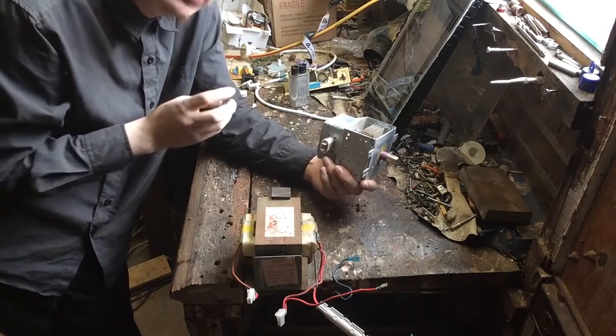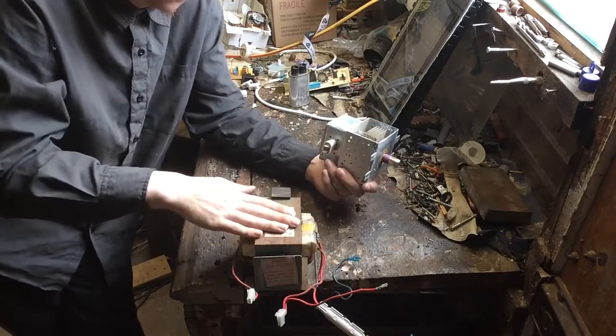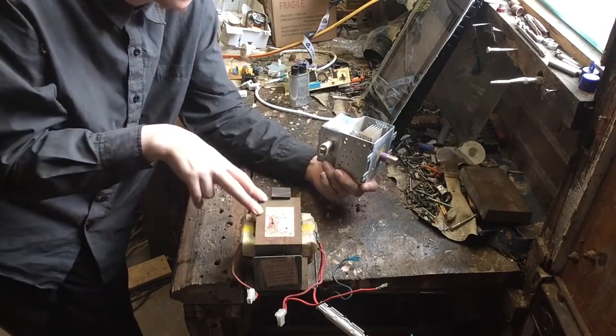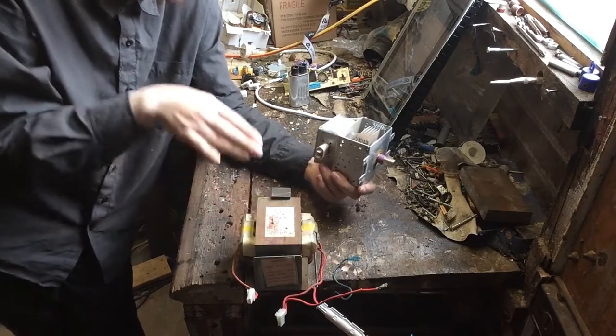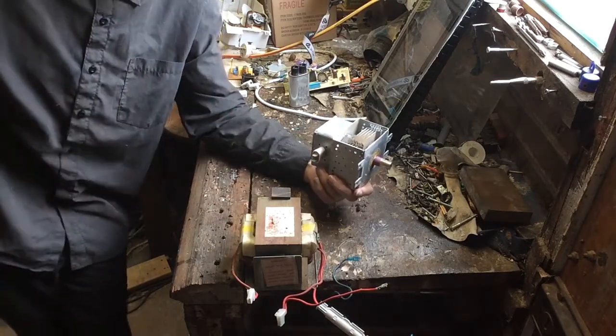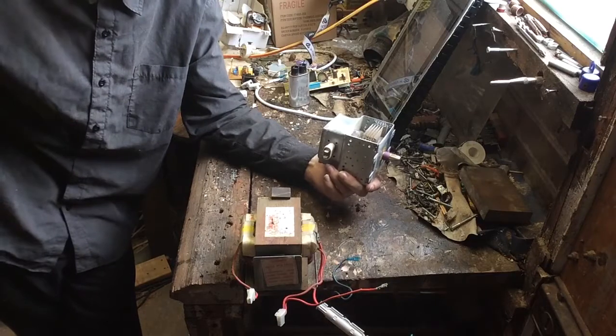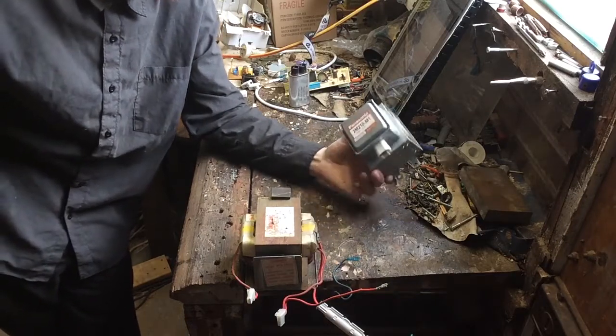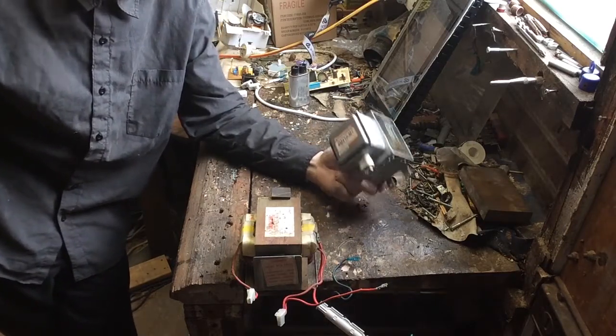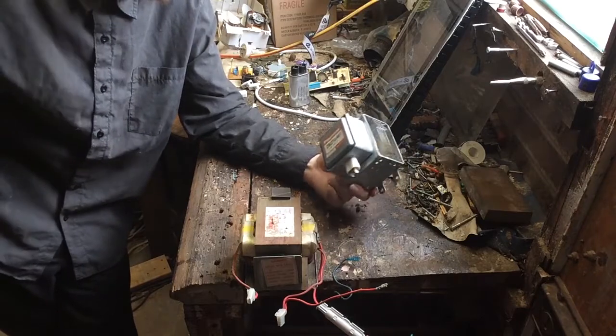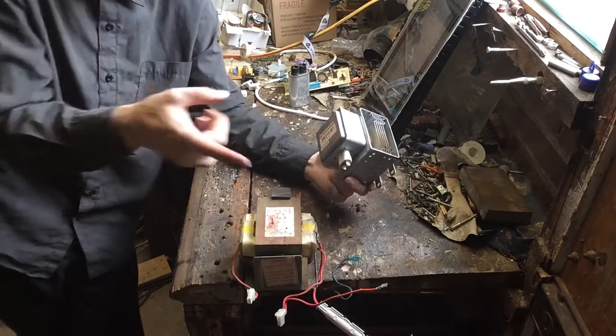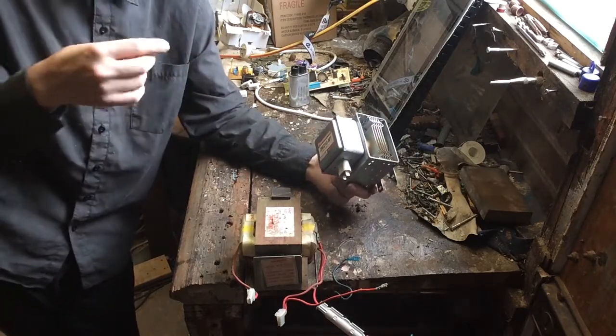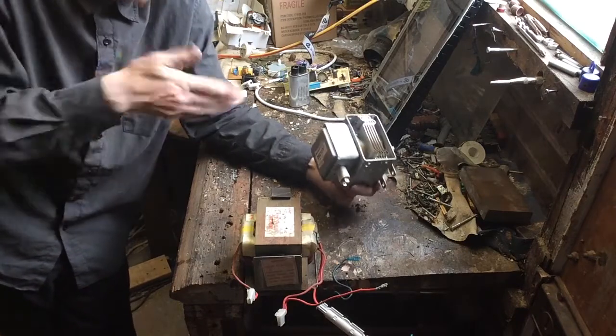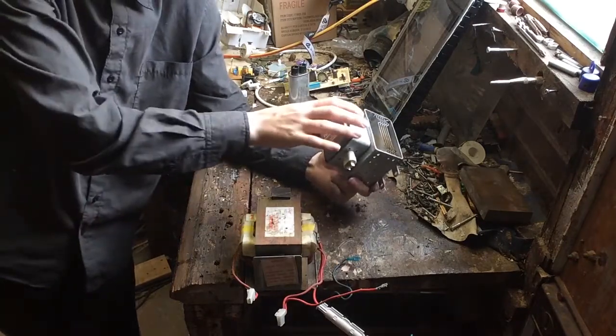You have to heat up the filament previously, which is also part of this transformer. But that's one part of this. The second part is the high voltage, the 2100 volts that we talked about before. That essentially provides a very high voltage 50-60 hertz signal to this. This then amplifies that and also amplifies it in terms of frequency, so it multiplies the frequency up using resonance.